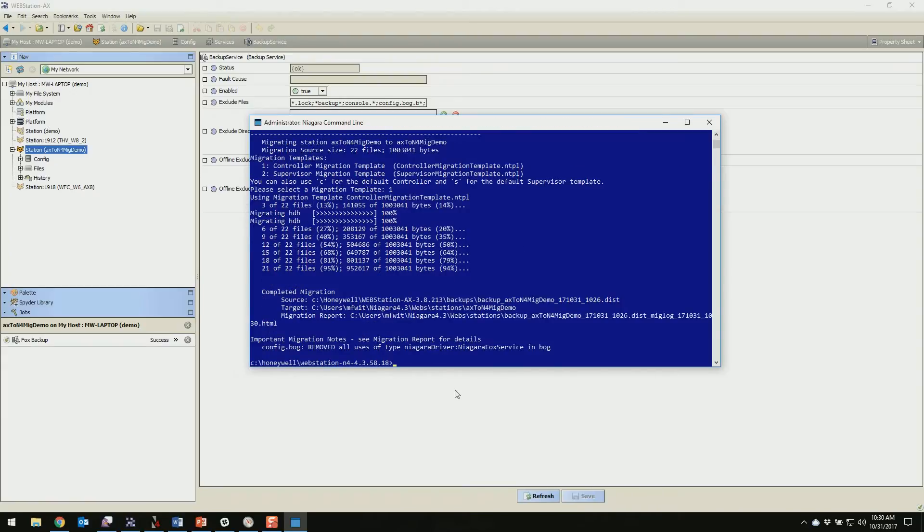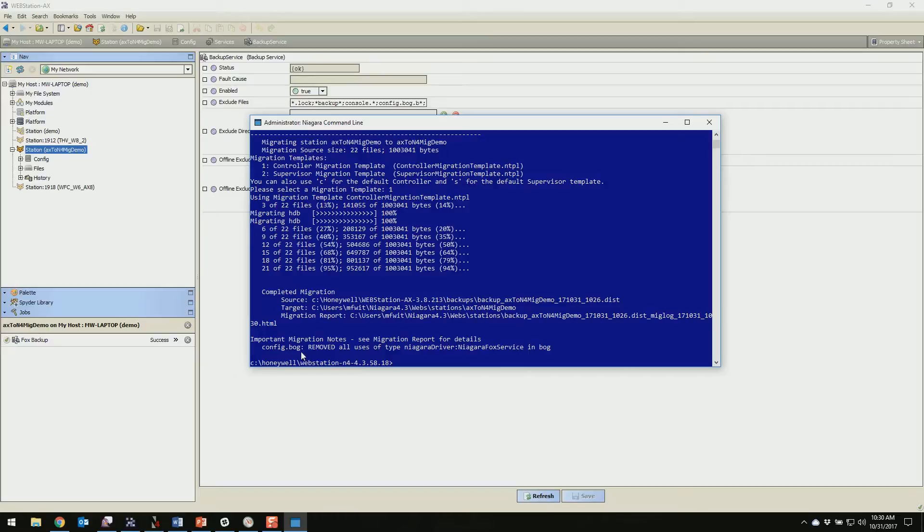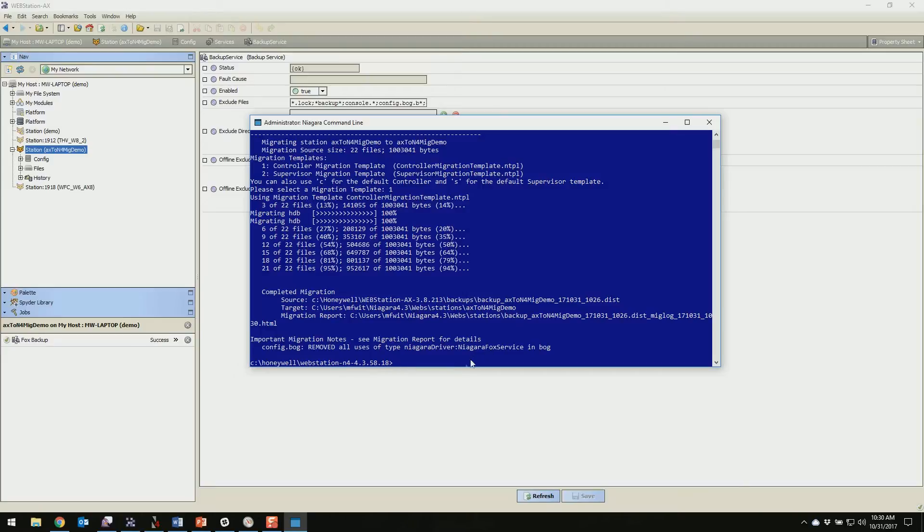You can see it migrated two history databases here. And the thing to keep note, we're finished now, but the thing to keep note of is at the bottom here, these important notes. For me it's just getting rid of the Niagara Fox service because that's moved now in Niagara 4, that's a normal thing you'll see that. But if you're missing modules in Niagara 4 that it needs to do this conversion, you'll see errors related to that here. So just keep that in mind when you're doing your migration, that's a pretty important piece.